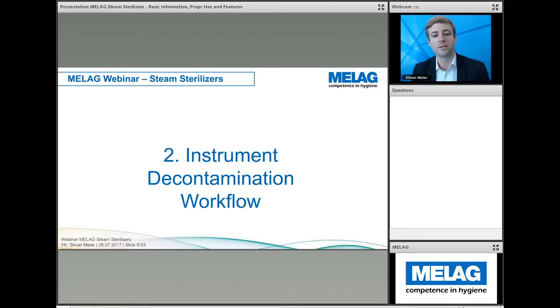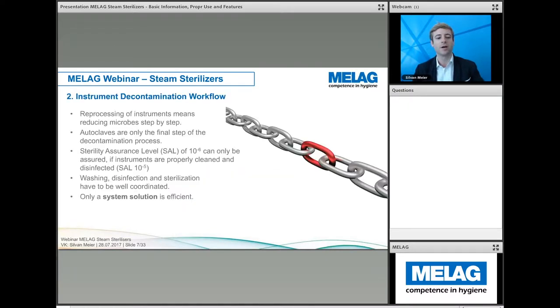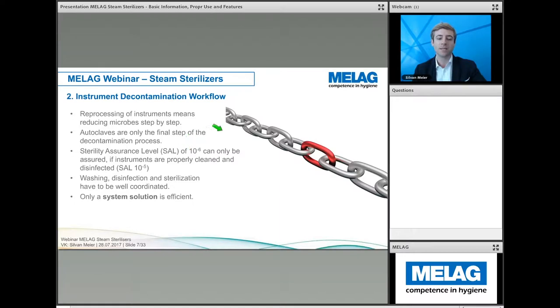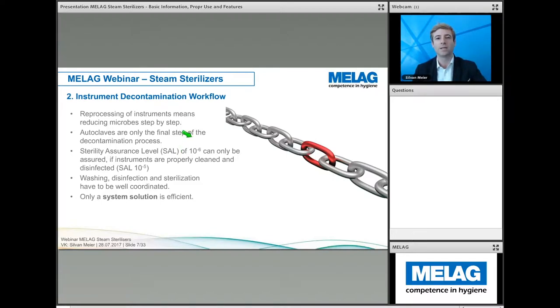All our sterilizers form an integral part of a very comprehensive hygiene workflow. Reprocessing instruments means we reduce microbes, bacteria, and germs step by step. The autoclave and steam sterilizers are only the final step of the decontamination process. To reach a sterility level of 10⁻⁶ — meaning that out of one million microbes, only one remains after a successful decontamination — we need a whole coordinated hygiene workflow. All instruments must be clean and disinfected before sterilization. Washing, disinfection, and sterilization must be well coordinated — like the links of a chain.